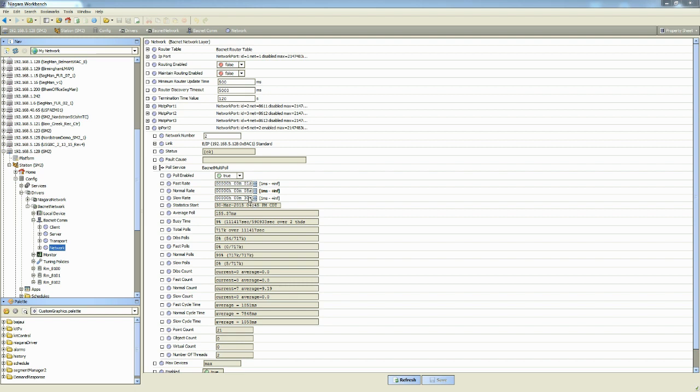So in conclusion, the goal here is to keep the normal polling rate higher than the normal cycle time. The cycle time is going to adjust depending on your number of rooms, number of devices and points in a segment manager will fluctuate from job to job. So it's important to visit this and make adjustments as necessary to improve the overall CPU usage on the segment manager.